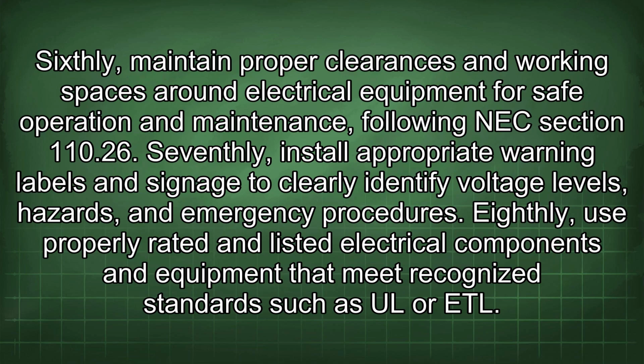Sixthly, maintain proper clearances and working spaces around electrical equipment for safe operation and maintenance, following NEC Section 110.26. Seventhly, install appropriate warning labels and signage to clearly identify voltage levels, hazards, and emergency procedures. Eighthly, use properly rated and listed electrical components and equipment that meet recognized standards such as UL or ETL.